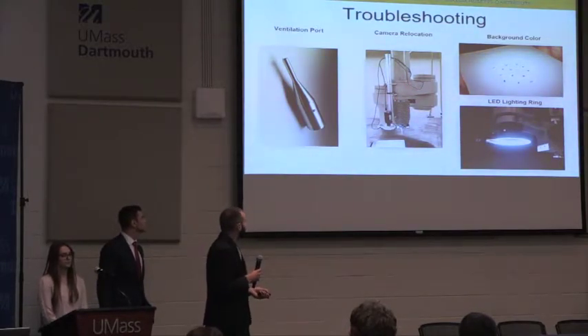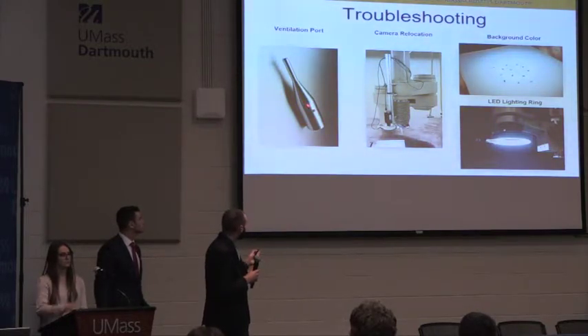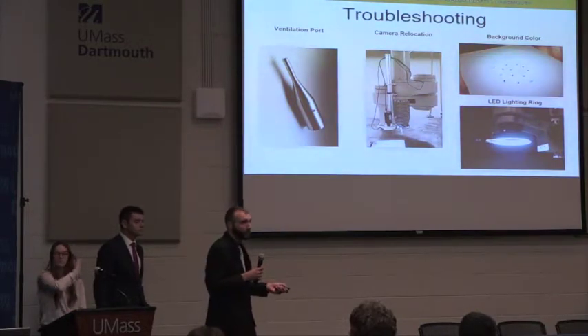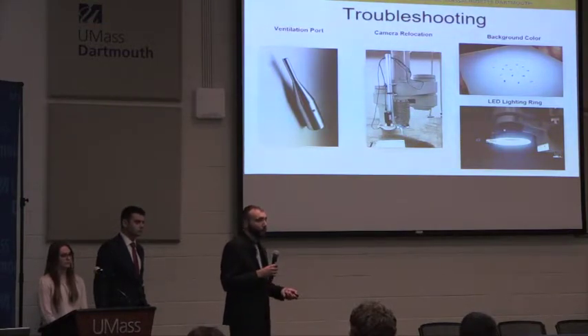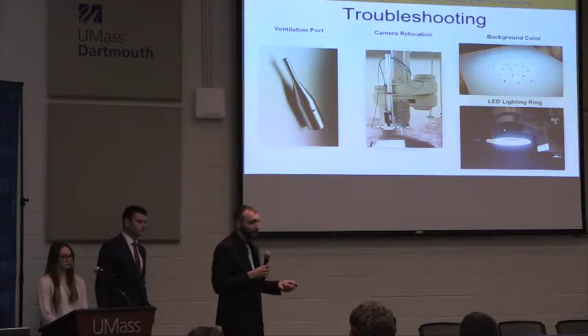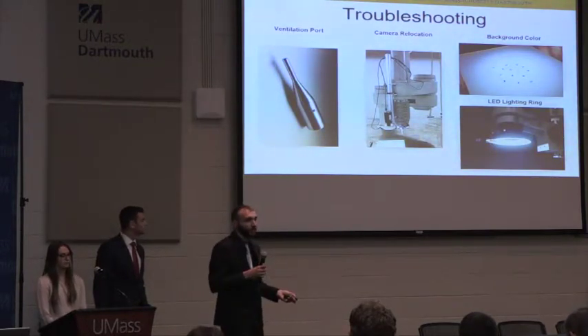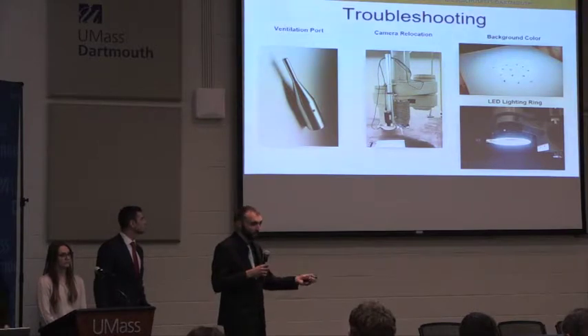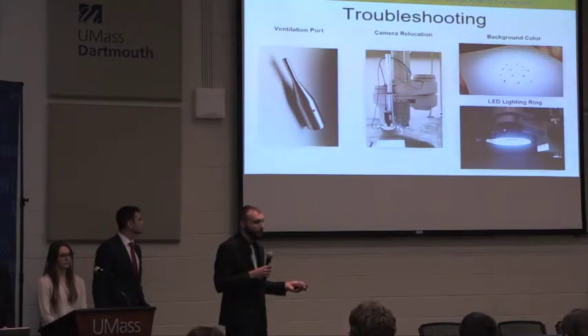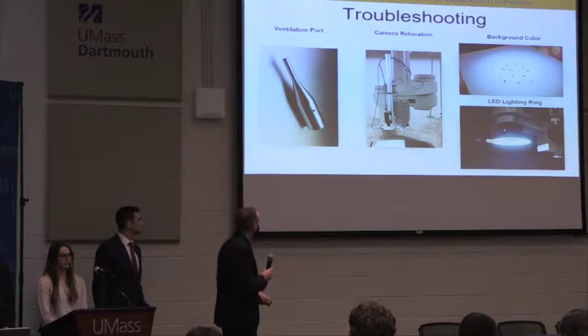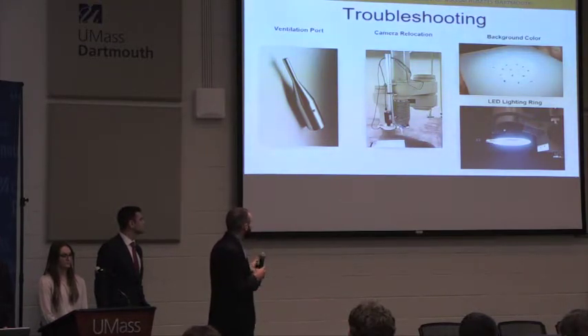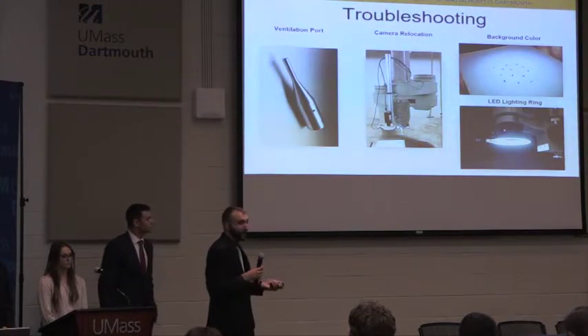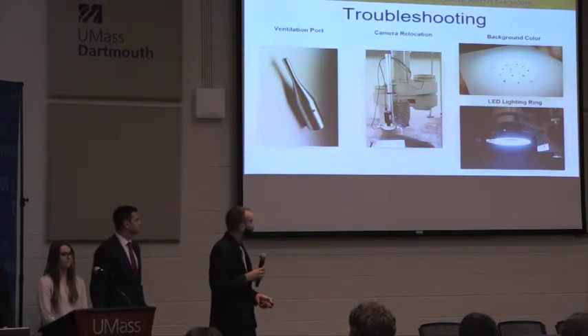To solve that, we drilled a 1/32 of an inch, very small hole in the tooltip that goes into the suction system. What was happening was something called airlock, where the negative pressure in the system was staying, even though we released the air. Drilling that small 1/32 inch hole helped significantly. We didn't have that issue at all after.